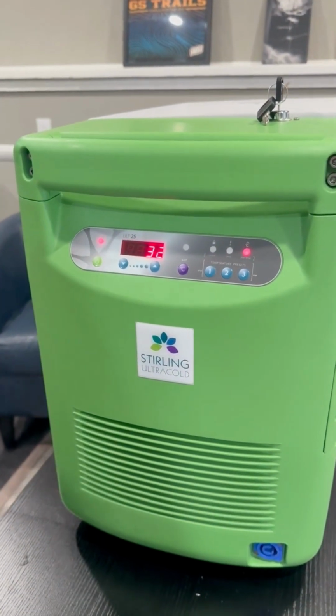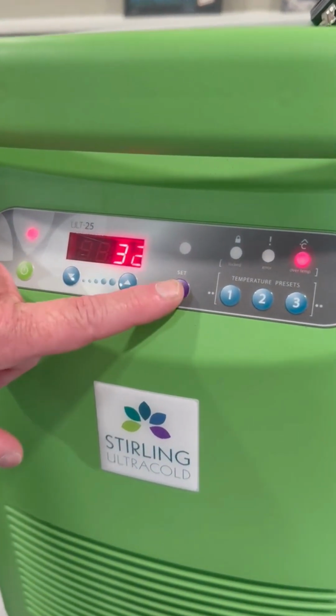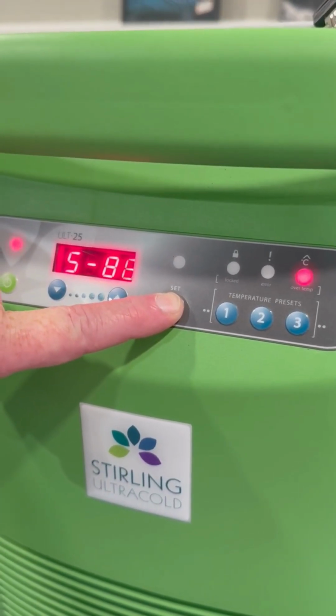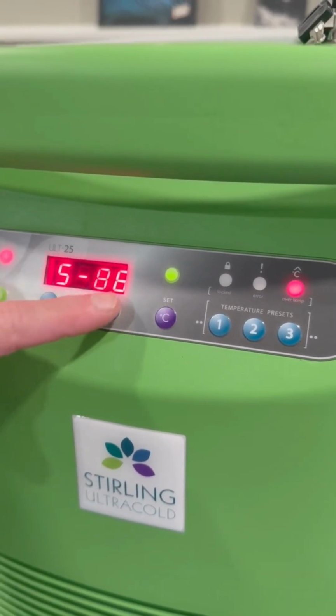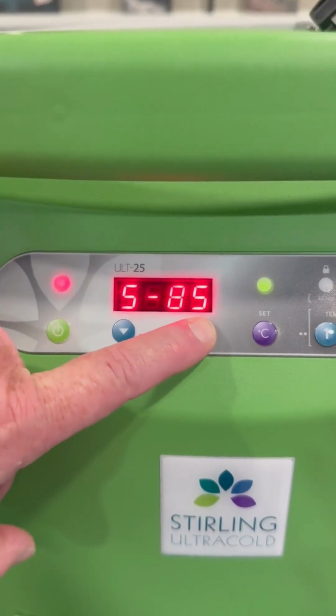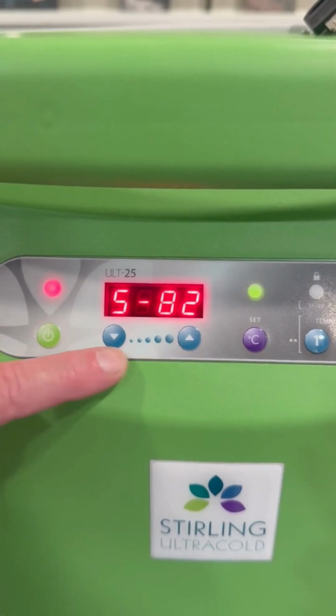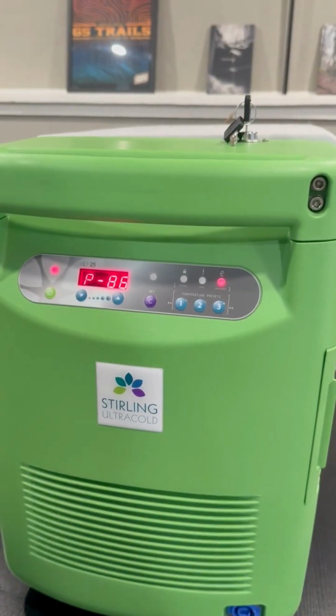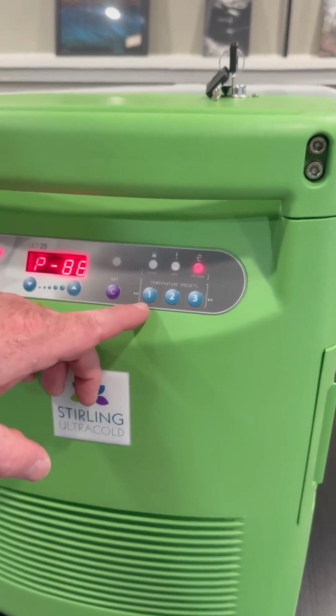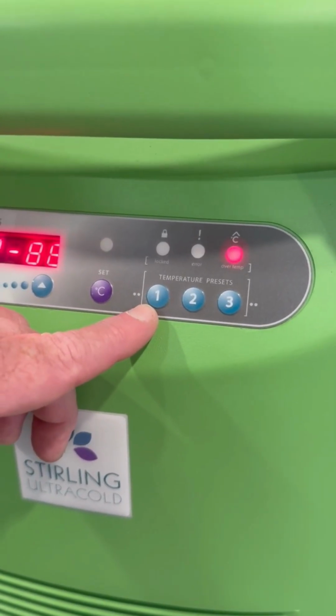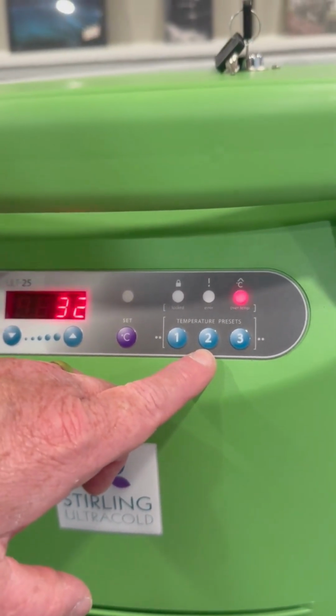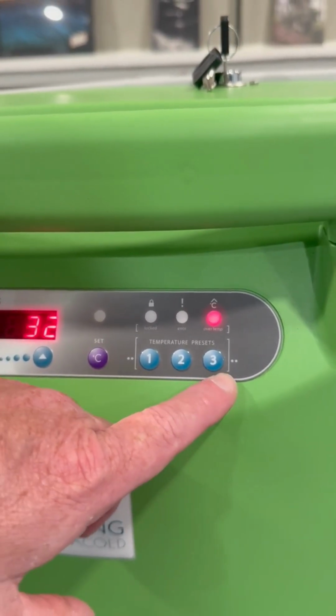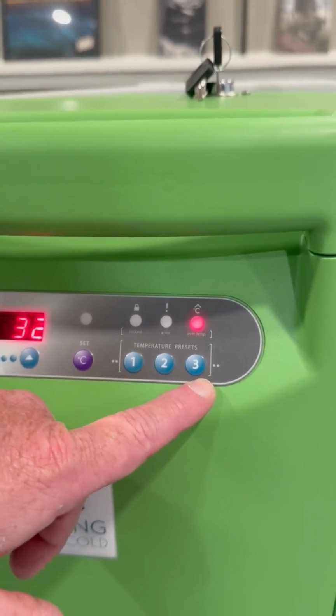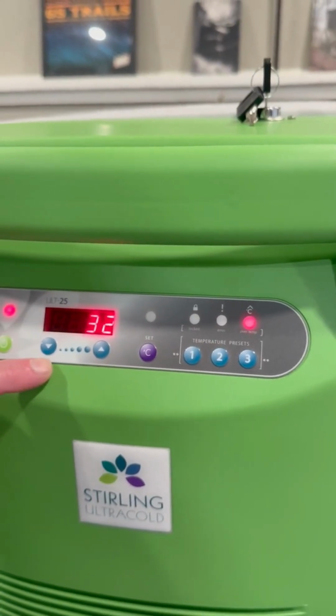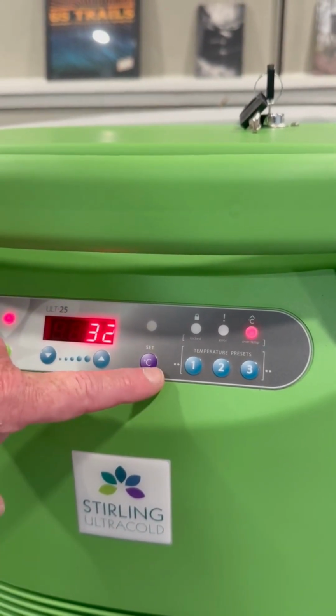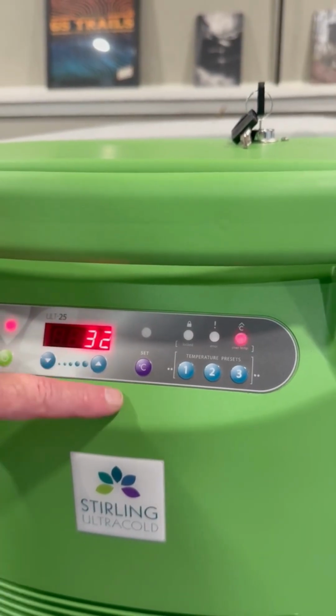In order to change the temperature, press and hold the purple C until the top light turns on. You will see a green light come on, and when that does, you are allowed to adjust the temperature to whichever degrees you want with these 2 arrow buttons. This unit will come with 3 preset temperatures. The first one, number 1, is negative 86 degrees Celsius. Number 2 is set to negative 40 degrees Celsius, and number 3 is set to negative 20 degrees Celsius. You can also range using these buttons over here with the up and down arrows. You can range after pressing this set point number. You can adjust your temperature to your preferred setting.